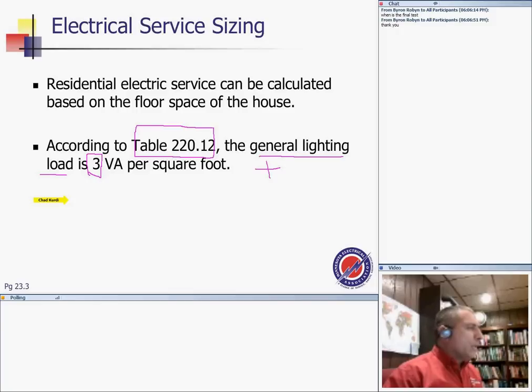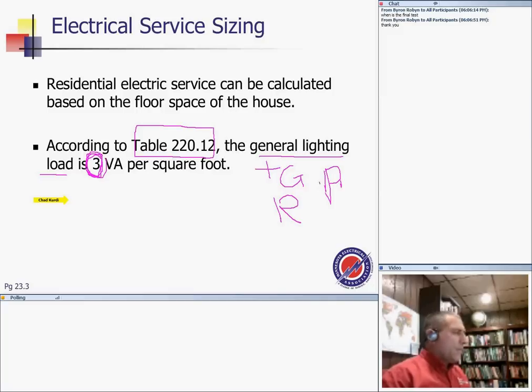This also includes general purpose receptacles. Only residential. General purpose receptacles are included in this 3 volt amp. Only for residential, the general purpose receptacle is included. And that's very, very important, guys.